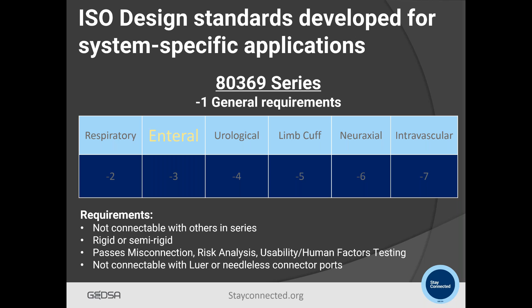Requirements are that they are not connectable with others in the series, and that they are rigid or semi-rigid material. They pass rigorous misconnection, risk analysis, usability, and human factors testing, and of course, importantly, not connectable with a Luer type of system. The Luer lock is something that is in use today, and that's part of the challenge that we have, is it's so commonly used across these categories. In the future, the Luer lock will be designated specifically for intravascular or hypodermic use.